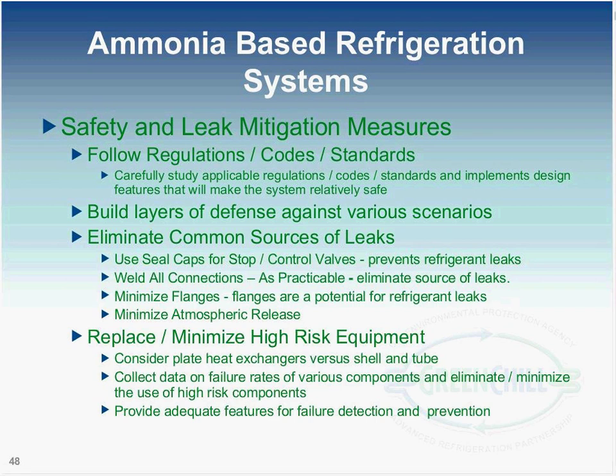And minimize the atmospheric release of the ammonia. Most of the codes will dictate that you install emergency pressure control systems, and you would like to connect all of them to a single point for treatment before you release the refrigerant to the atmosphere.